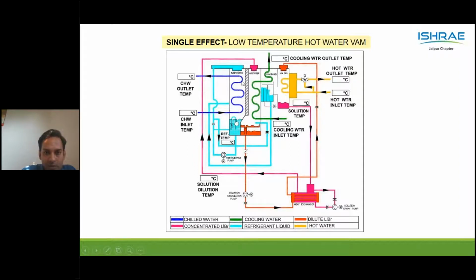Here, which is all the producing the water vapors, which is going to the absorber side. The green color is my cooling water line. The orange color line is the weak solution of the lithium bromide, which is diluted by absorbing the water vapors, via the pump and the heat exchanger it is going to my heat exchanger, which is heating the lithium bromide, and in the condenser the water refrigerant condenses and circulates again.